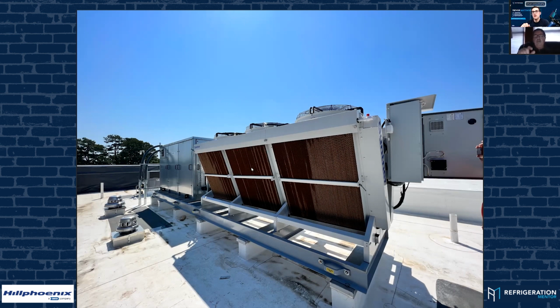Okay, so let's just get this straight. On these ones, you'll have a pre-filter and a post-filter. So this would be the pre, the outdoor ambient humidity, and then you'd have one behind the pad. Is that correct? Yep. And measuring. What it does is when we reach two parameters we set in our controls in here, we'll modify the programming for an 80% fan and 75 degrees. Some areas, if it's a little warmer, we might go to 73, but basically 75 degrees. So you have to have two things at one point to make the fan want to go to pre-cool, it's called. So on a Güntner, 80% fans and 75 degrees, we're going to go pre-cool.